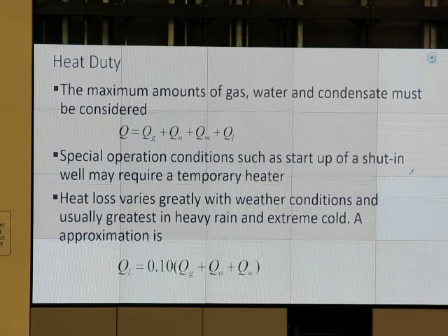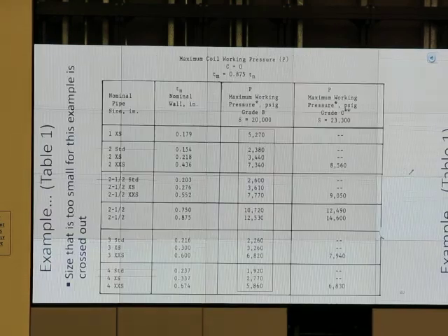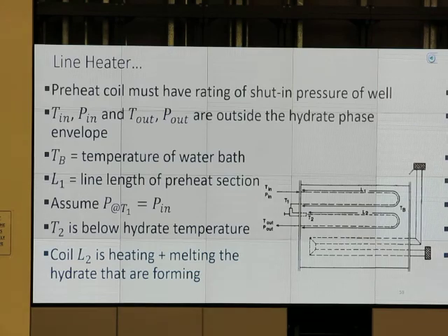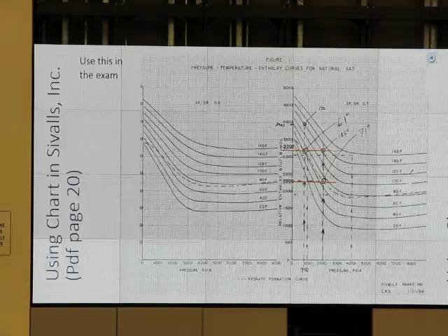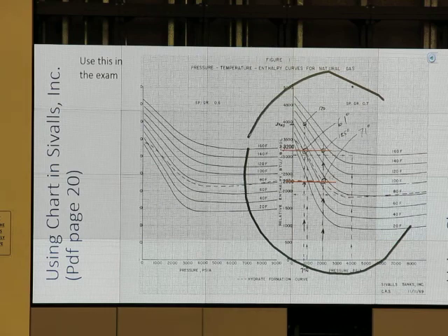I like your answer, but it's not quite precise. Let me give you the precise version, the very short answer and still correct. We use this. Typically, we heat just to reach the hydrate temperature in the first pass. So wherever it's coming in, we heat just to reach the hydrate temperature. And if I want it to go out at 120, I heat more.